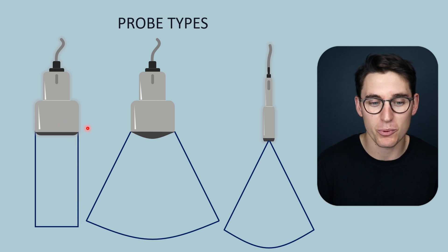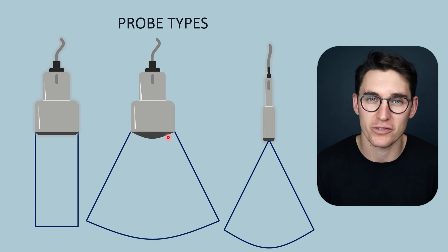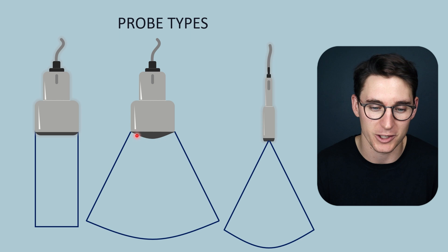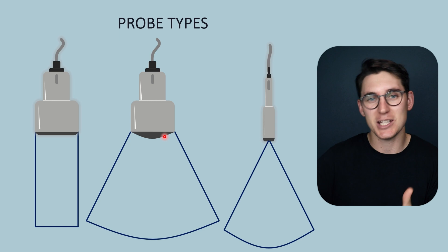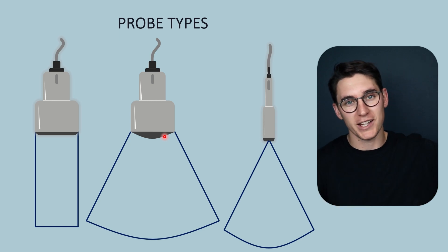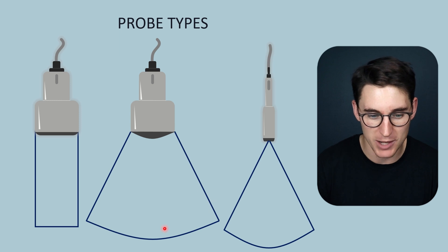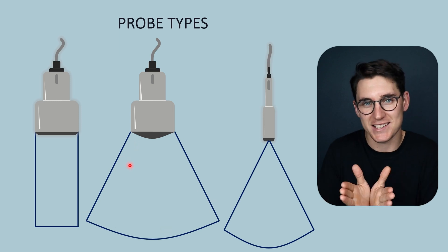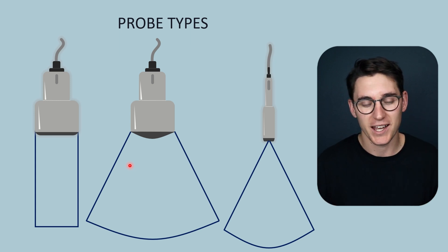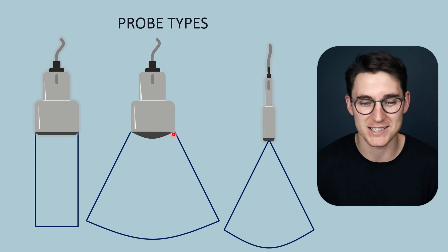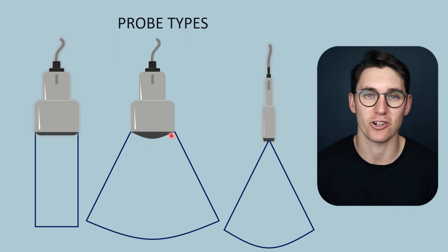We can take this same probe and curve the front of the probe. This is what's known as a curved linear probe or a curvilinear probe. You can see our field of view diverges out — as we get deeper into the tissue we are sampling a greater area of that tissue. This shape is what's known as a sector, a part of a circle like a slice of pizza or a slice of cake. Here we've got what's known as a blunted sector because the front of the probe blunts the apex of the sector.